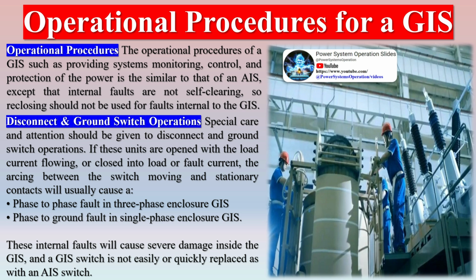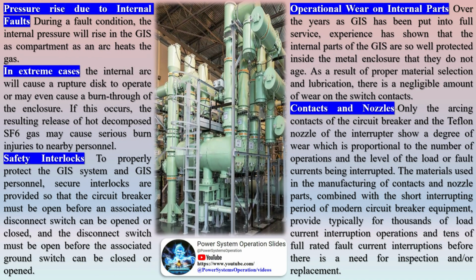The operational procedures of a GIS such as providing systems monitoring, control, and protection of the power is similar to that of an AIS, except that internal faults are not self-clearing, so reclosing should not be used for faults internal to the GIS. During a fault condition, the internal pressure will rise in the GIS's compartment as an arc heats the gas. In extreme cases, the internal arc will cause a rupture disk to operate or may even cause a burn-through of the enclosure. If this occurs, the resulting release of hot decomposed SF6 gas may cause serious burn injuries to nearby personnel.